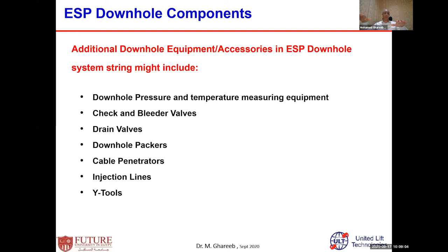But if it is not stopped, because you stop the well due to any reason or problem, such as a power shutdown, and the power automatically comes back again while the fluid is still going down, the flow rotates the pump in reverse. If you start the unit, it will try to run in the standard rotation, then the shaft of the pump, the motor, and the seal will be twisted.